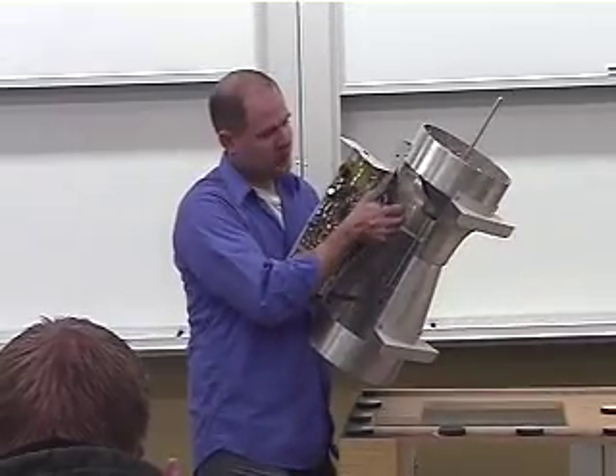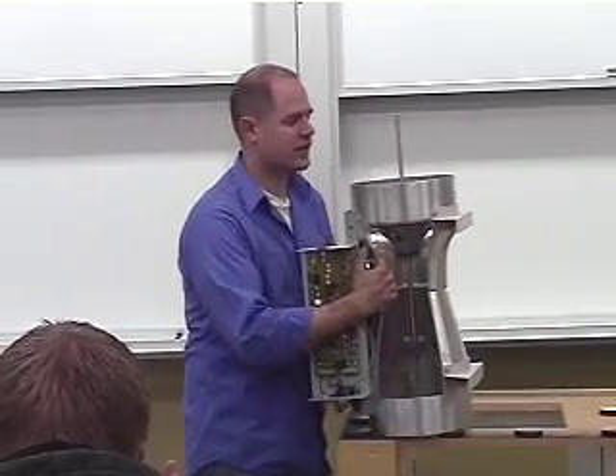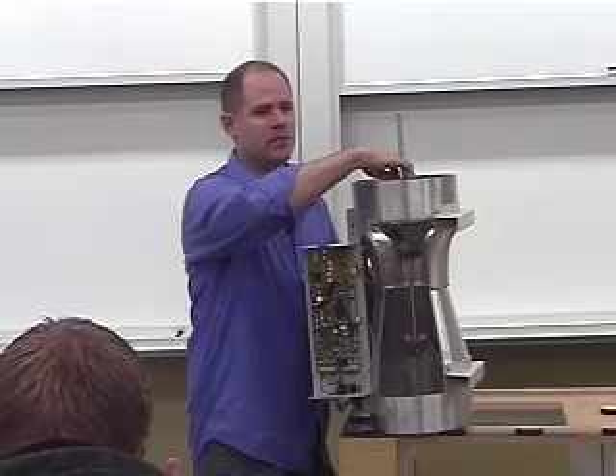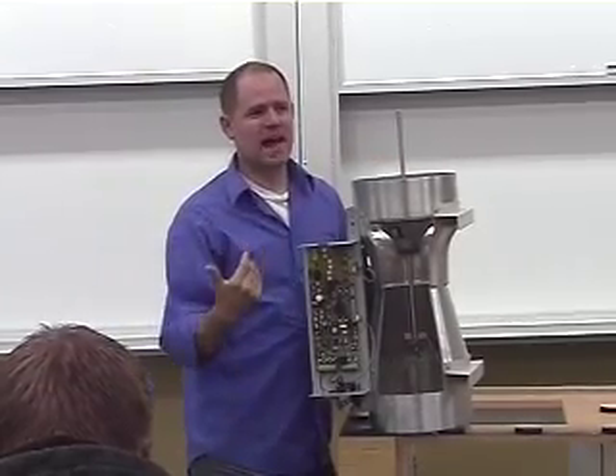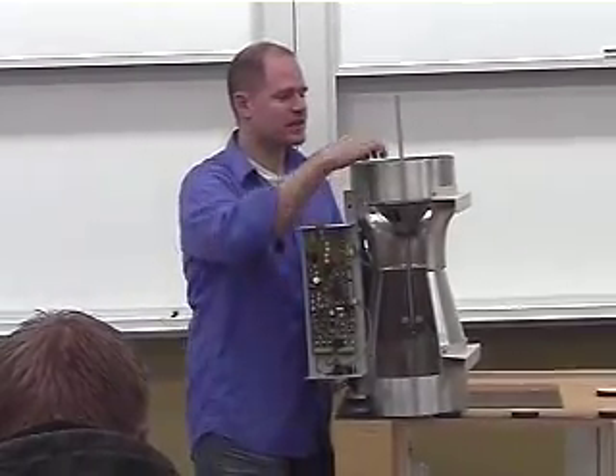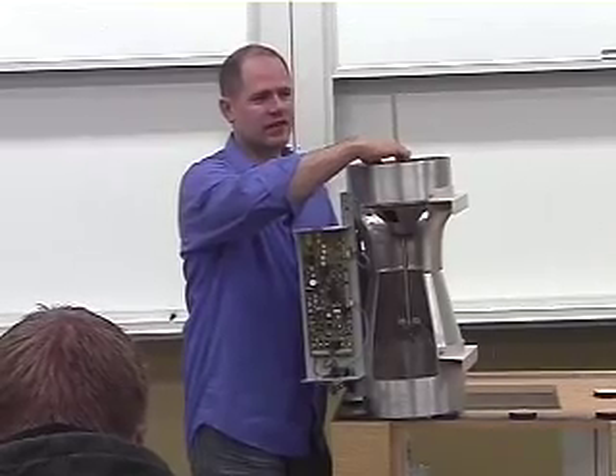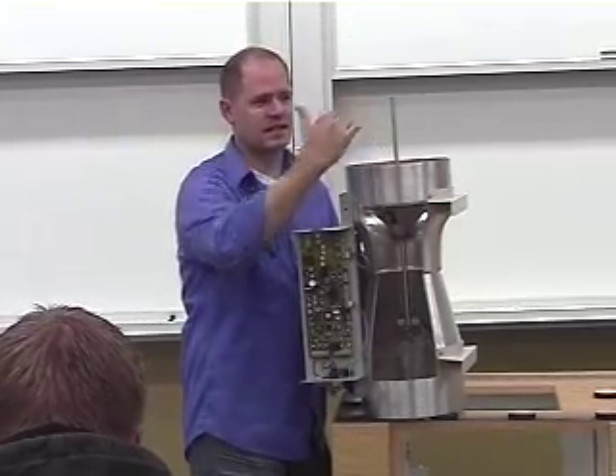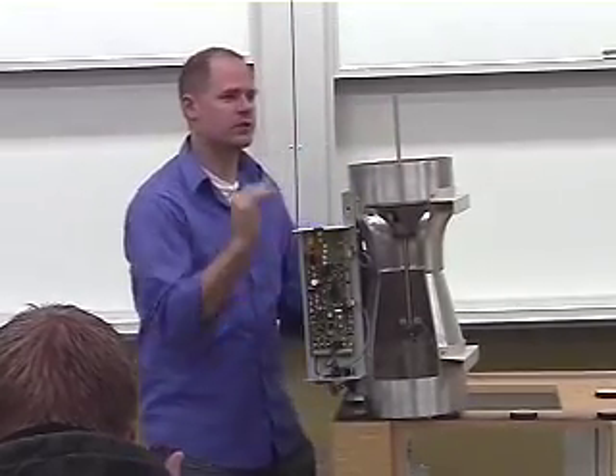If you have it going with a vertical downflow, all of a sudden you have the spring weighted down by the cone. So it has to adapt for that, so they make the spring a little bit stiffer, so that the air pressure across here makes the same distance change as it would if it was horizontal.